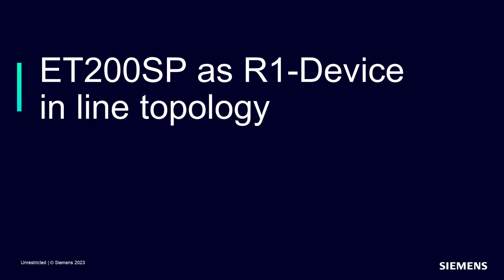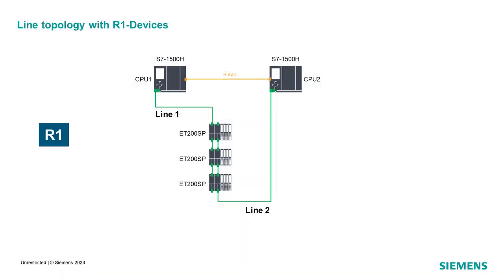As an example, we will use the line topology. This topology consists of a redundant controller S7-1500H, a redundant network in line, and ET200SP stations as R1 devices. By design, a station R1 has a redundant interface module on board. The first interface module belongs to line 1 and the second one to line 2.